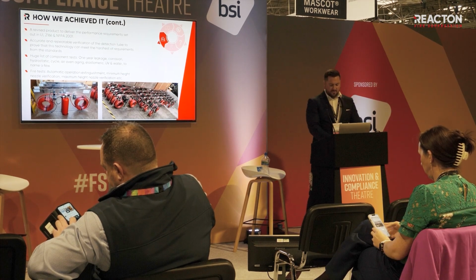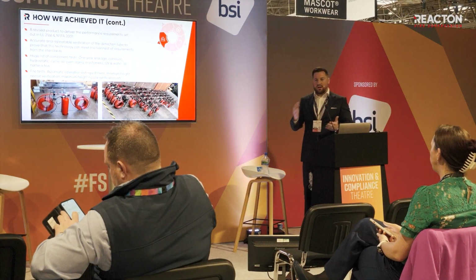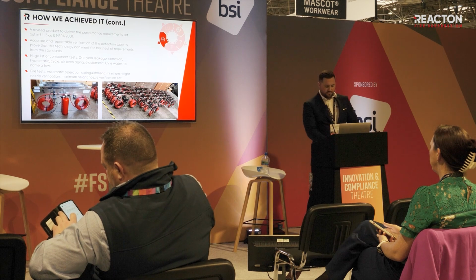But I've got a few videos here so you can see some of those tests. The first one that comes up here is section 37.3, a nozzle distribution extinguishment test. We have 10 cans in there filled with heptane, and they're mounted in strategic places. You have a baffle and you need to be able to put them all out. This standard requires full extinguishing. There's no allowance for saying I managed to get a certain number put out and I average that and I'm okay. It's full extinguishing.